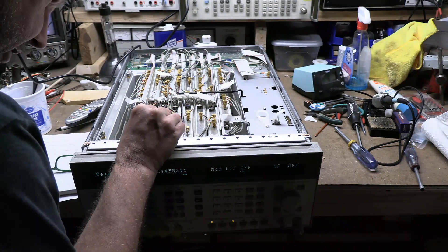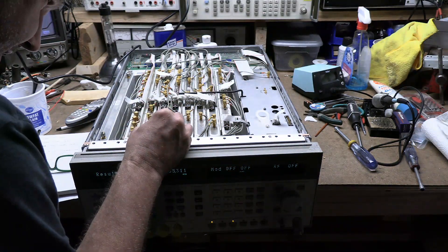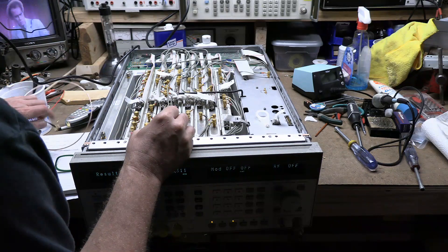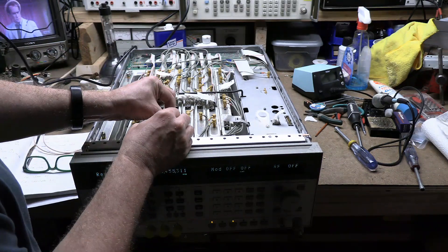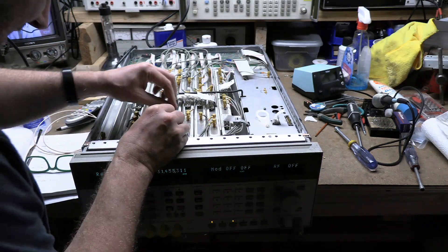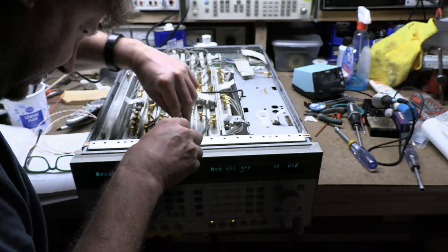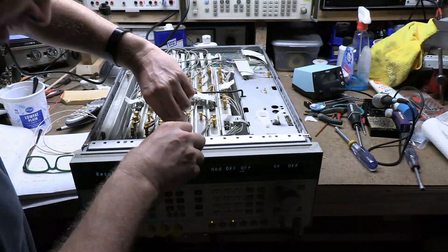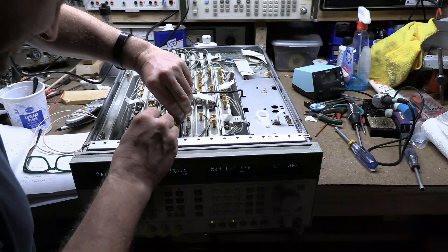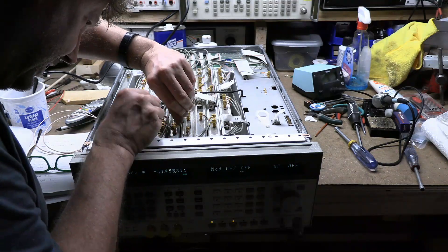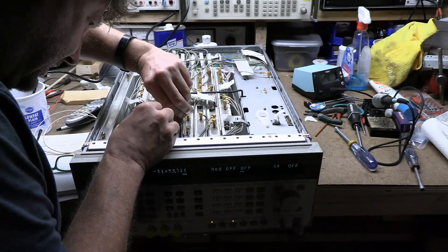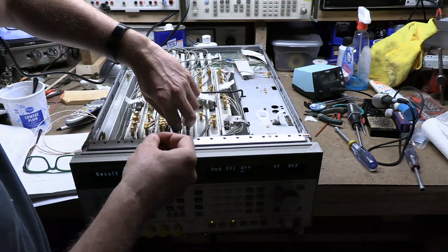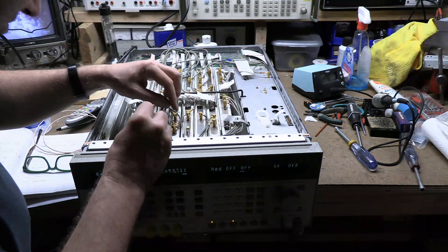Now the deal is, if I run test 4A and I get a positive result, whatever module it indicates, you just replace it. There is no component level repairing in these things. There is no schematic.